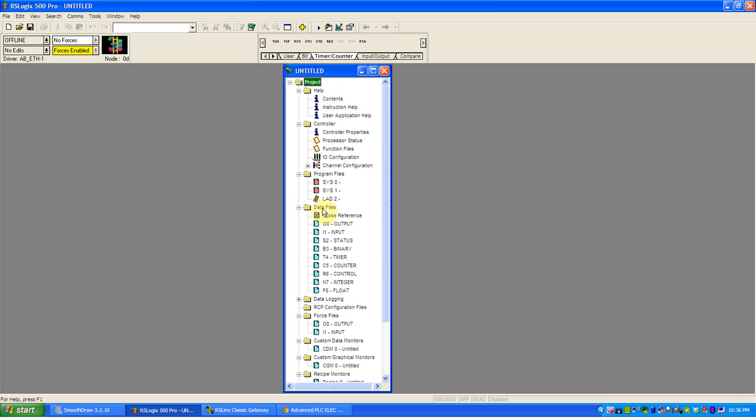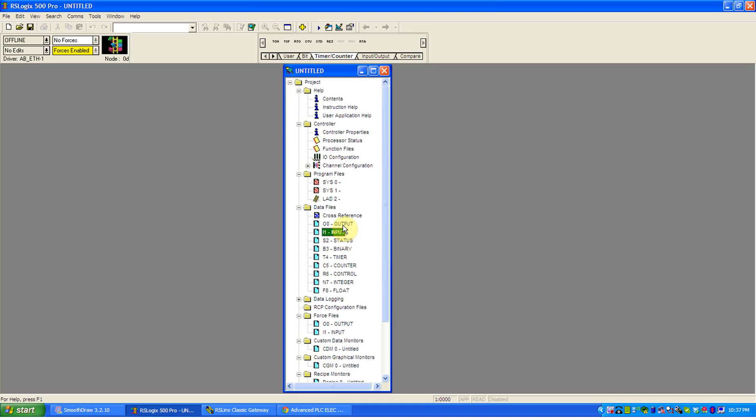The intent of this video is talking about this one here called data files. All PLC logic is intended to just manipulate or make decisions based on these data files. So I look at an input and I change an output because of it. You press start, I turn on an output which starts something, or I have an internal flag, a binary system done, system starting, safeties enabled, stage one complete, or timers, how long something's happened, T40, T41. You sort of know how all this works.